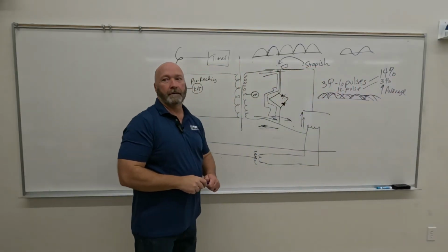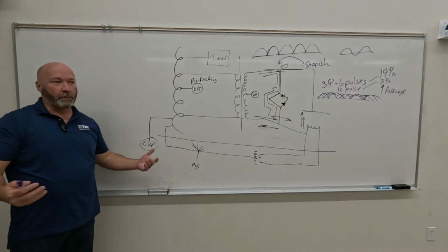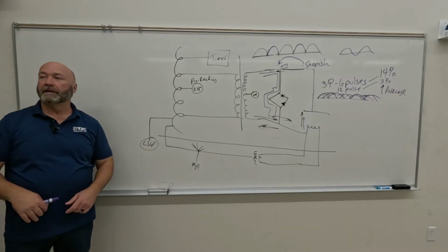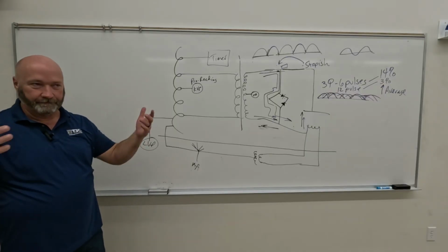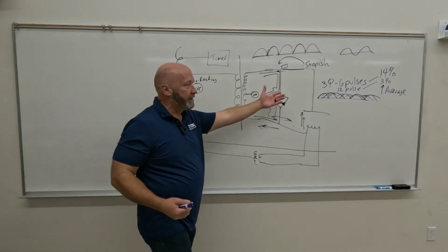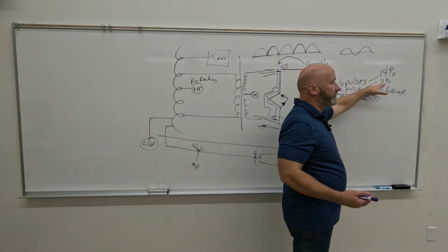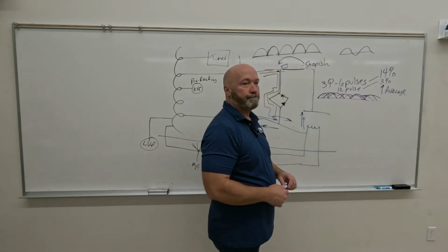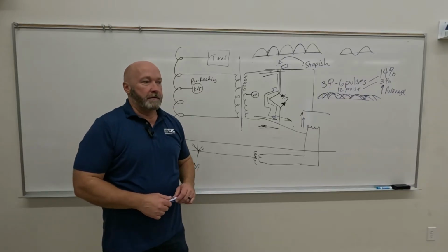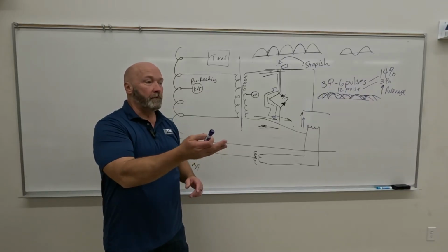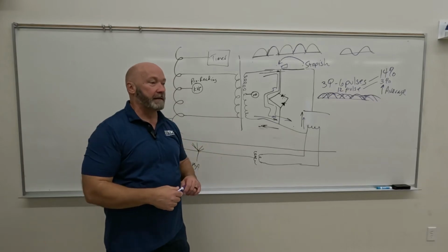Okay, so what happens there? We get a higher average, right? So our beam energy doesn't drop. Say we set 100 kVp, it doesn't drop more than 3% on those peak energies. So your lowest is 97 kVp. What's that? Yeah, so it might drop to 97.